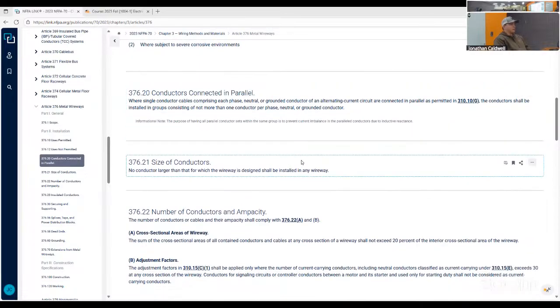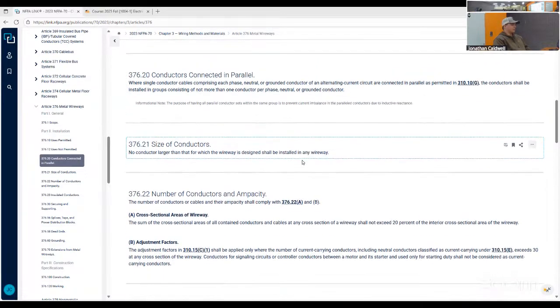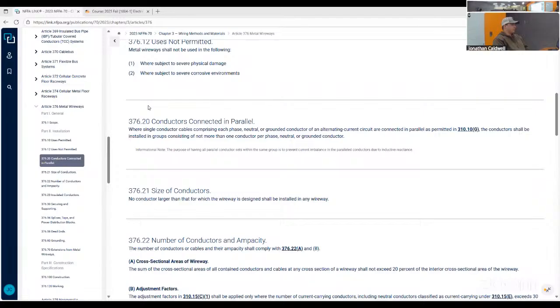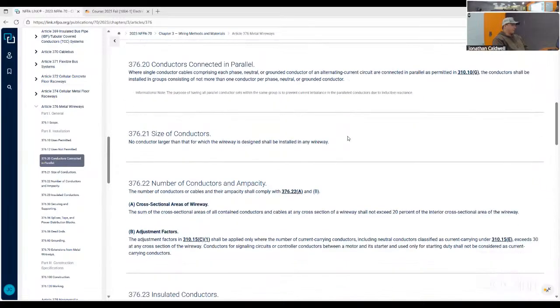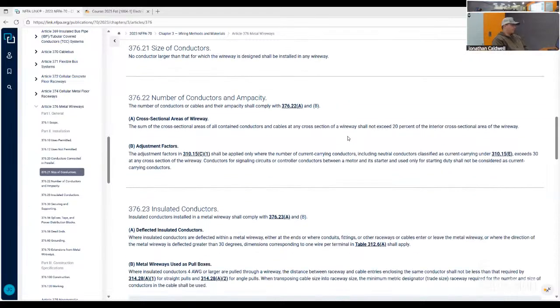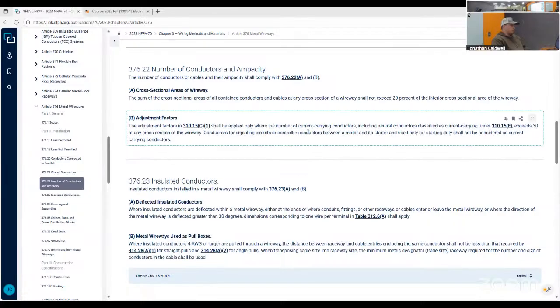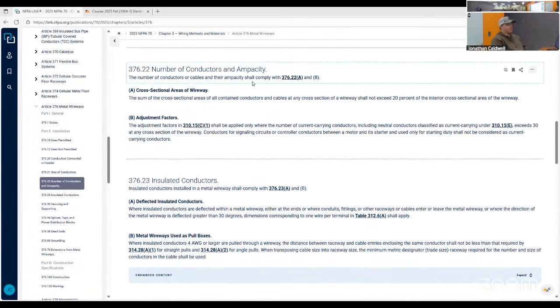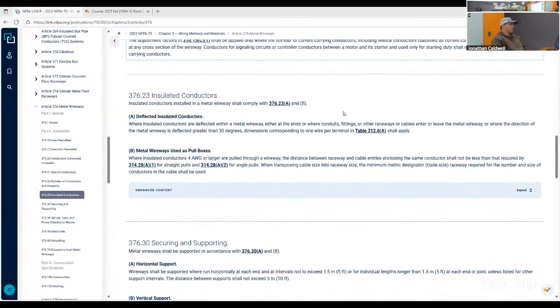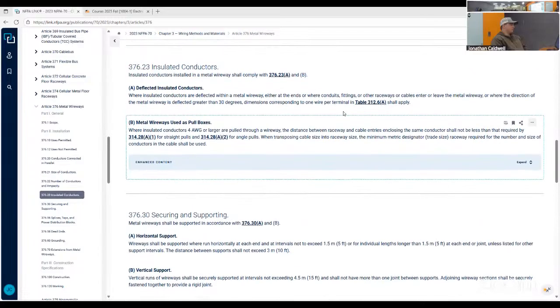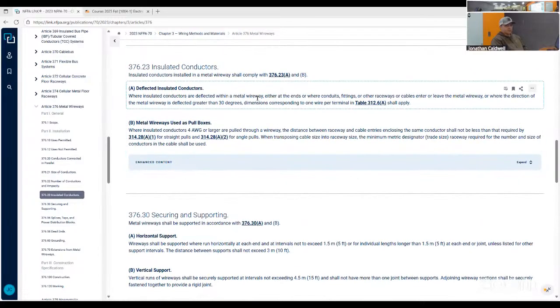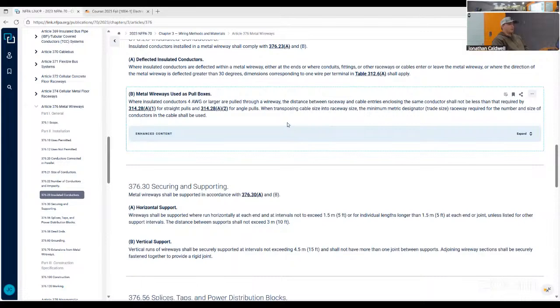Because you'll also see in ISU that they use it for access control. And conductors connect in parallel, the same. And then this one's also 20%. There is a derating table for wireways, so make sure you understand it, because it is a lot different from conduit, I think. If I remember right, the maximum you can go with number 12 is like 26 of them in one wireway. That also depends on the size of the wireway.